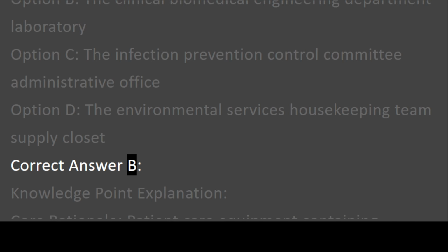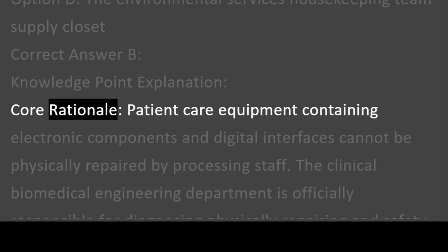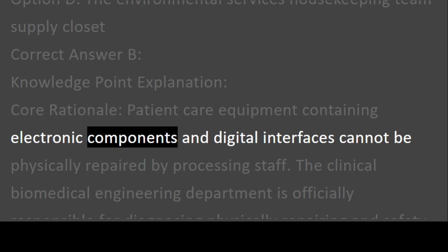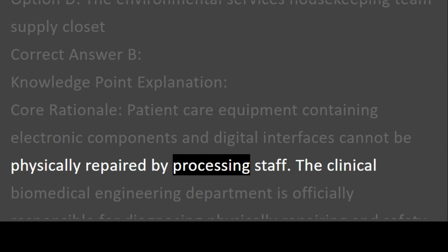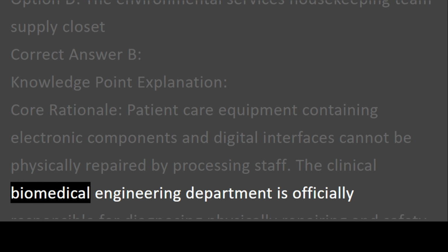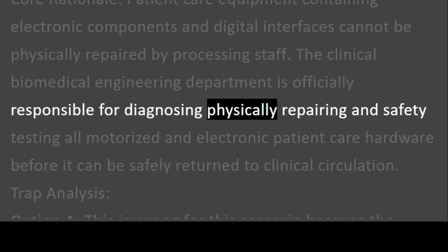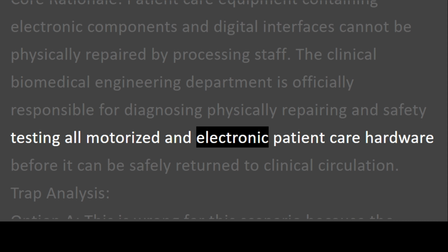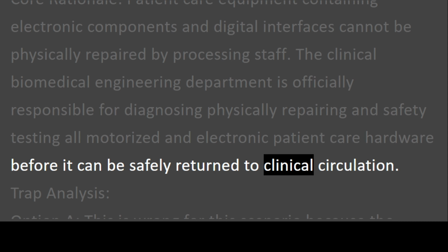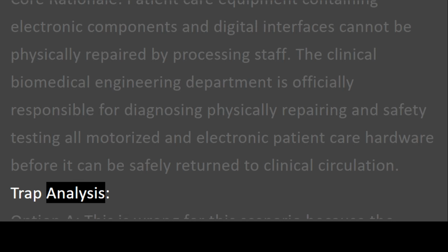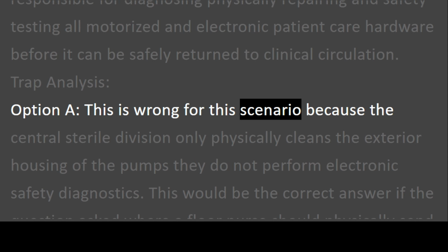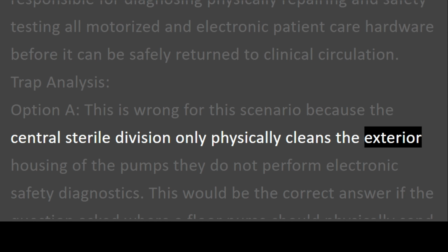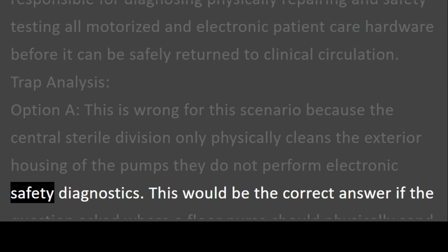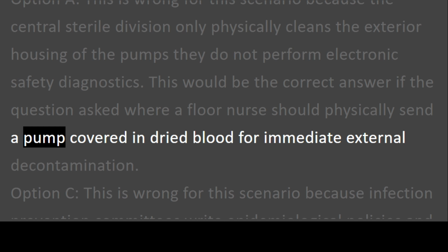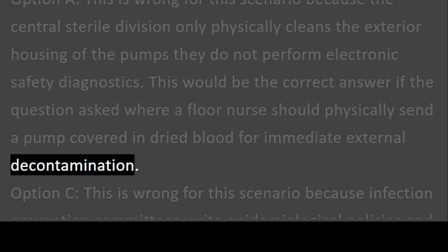Correct answer B. Knowledge point explanation. Core rationale. Patient care equipment containing electronic components and digital interfaces cannot be physically repaired by processing staff. The Clinical Biomedical Engineering Department is officially responsible for diagnosing, physically repairing, and safety testing all motorized and electronic patient care hardware before it can be safely returned to clinical circulation. Trap analysis. Option A. This is wrong for this scenario because the Central Sterile Division only physically cleans the exterior housing of the pumps. They do not perform electronic safety diagnostics. This would be the correct answer if the question asked where a floor nurse should physically send a pump covered in dried blood for immediate external decontamination.